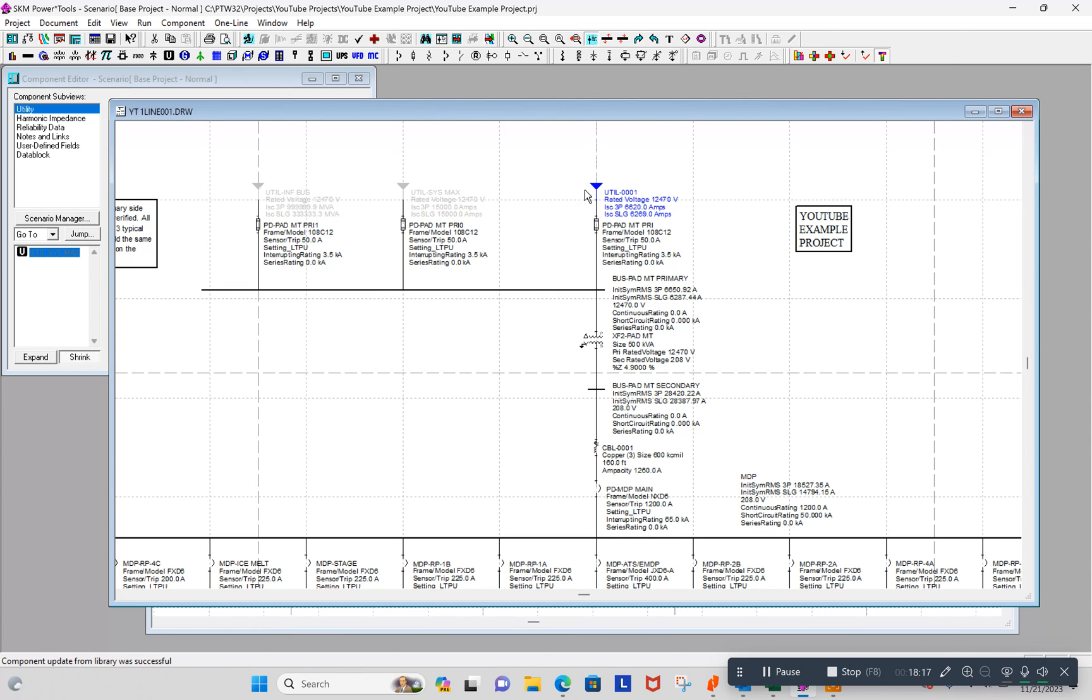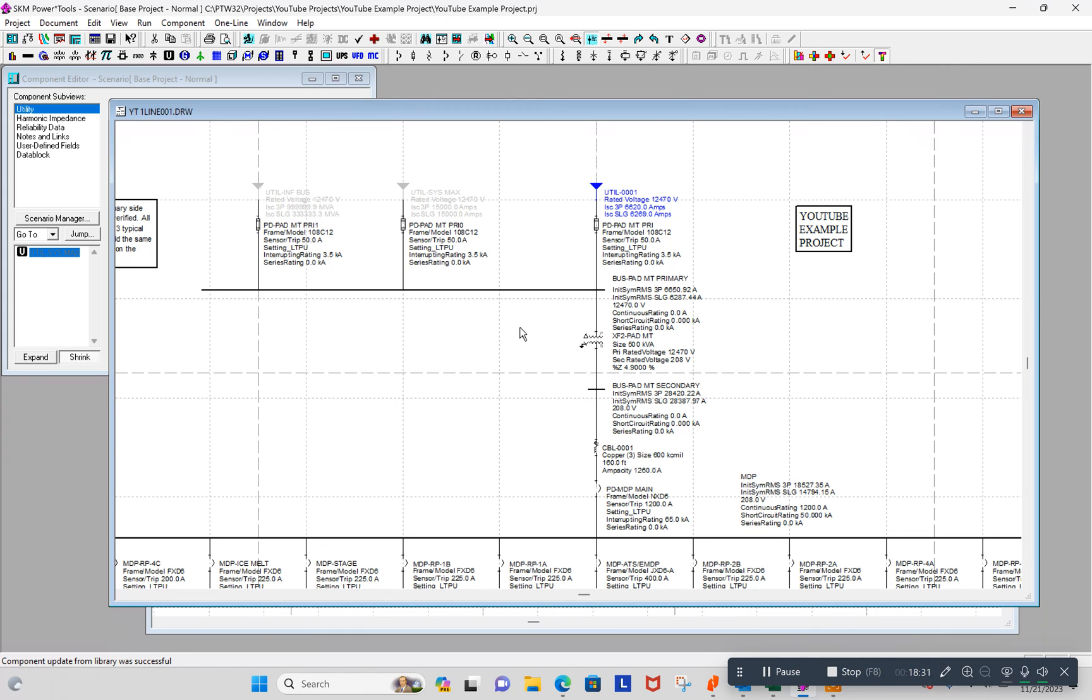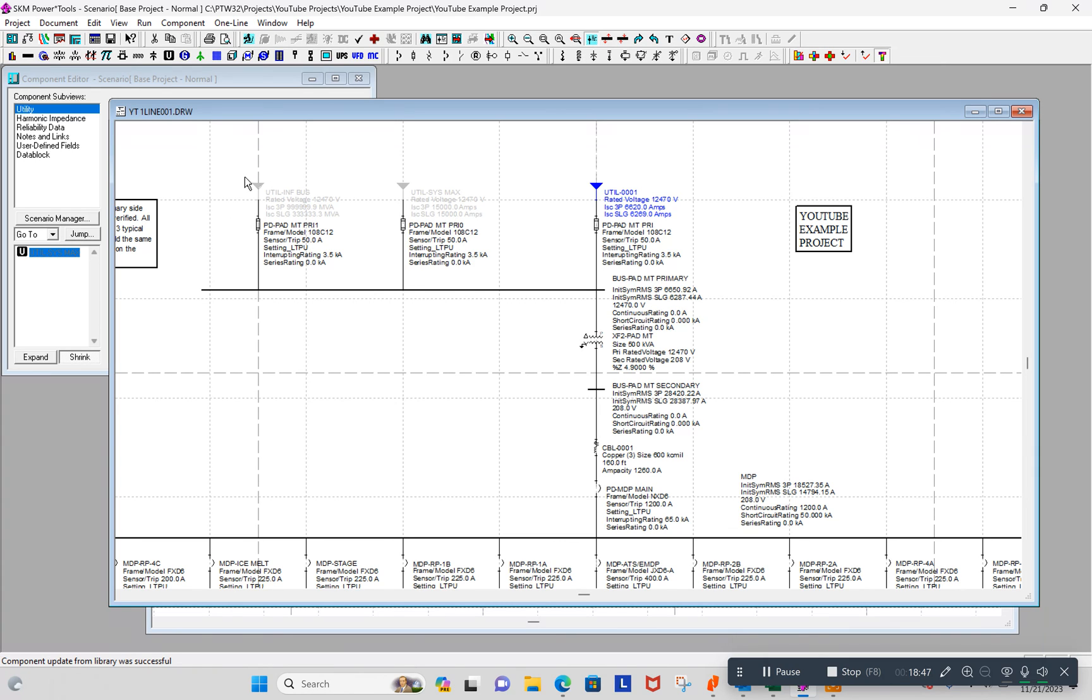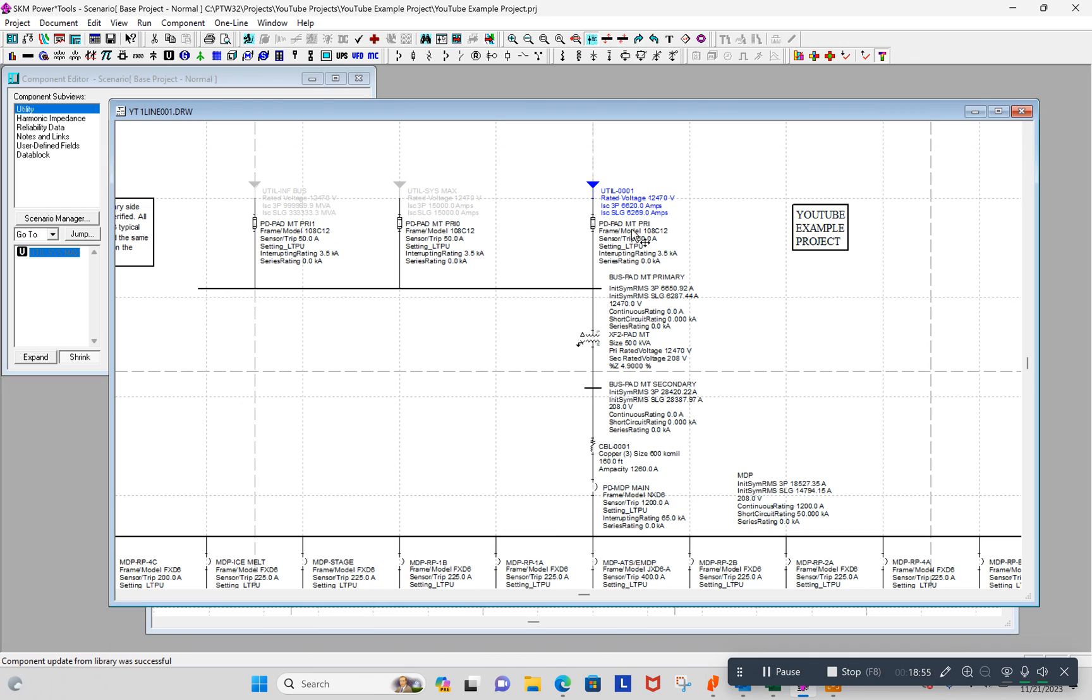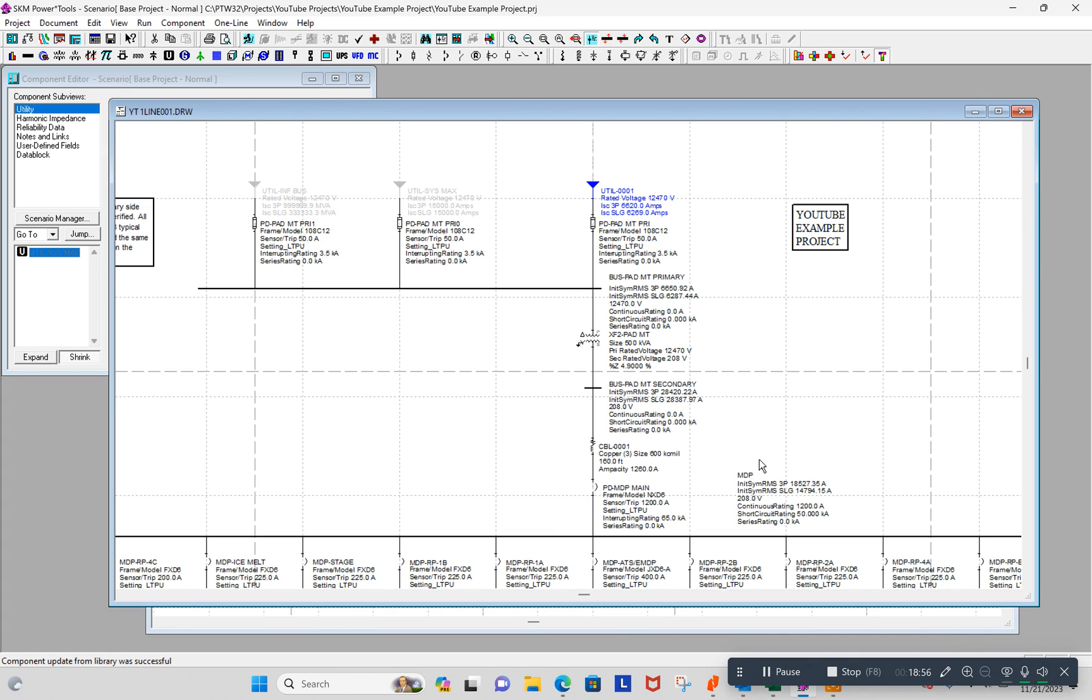Which, by the way, which is what I would probably want to run if I'm just speccing equipment out. Not for purposes of doing arc flash studies. For arc flash studies, you want the most accurate utility information that you can. But if it's a new job and you're wanting to spec AIC and SCCR ratings that you definitely know will be adequate, then I probably would run that into a scenario where I am using infinite bus and I would have all the motors on to get the motor contribution. But this is just kind of an easy way to check things without having to use the scenario manager for that.